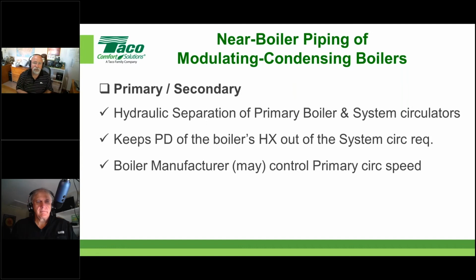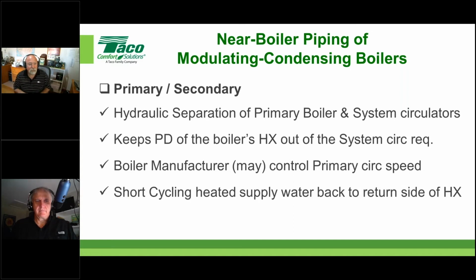Again, as I mentioned a couple of slides before, sometimes the boiler manufacturer will give you control of that primary circulator, which we'll say is the boiler circulator, and then we can get control of the temperature differential through the full cycle of the boiler. And again, we'll do some exercises here that'll give you an idea of what I'm talking about as far as what that temperature differential really could and can be. Then we'll show you this in better pictures as well, but that's just another bullet to talk about what primary secondary can do.